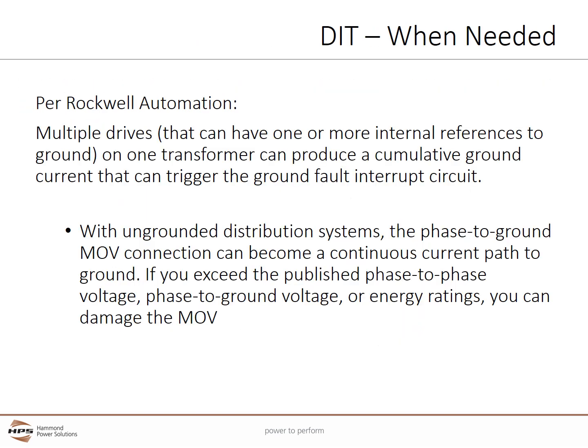In this case, we are going to quote Rockwell Automation, but other VFD manufacturers have made similar statements. Multiple VFDs that can have one or more internal references to ground on one transformer can produce a cumulative ground current that can trigger the ground fault interrupt circuit. With ungrounded distribution systems, the phase to ground MOV connection can become a continuous current path to ground. If you exceed the published phase to phase voltage, phase to ground voltage, or energy ratings, you can damage the MOV and cause the VFD to fault. Having each VFD on a drive isolation transformer eliminates this issue.